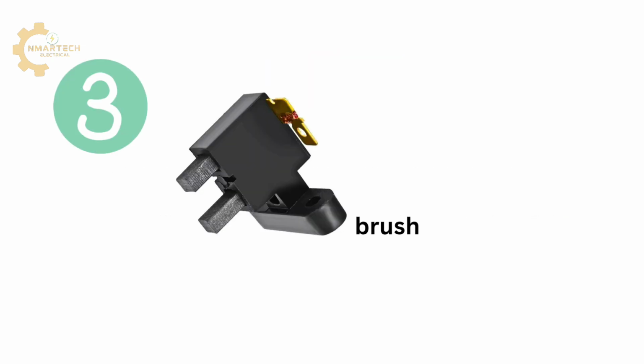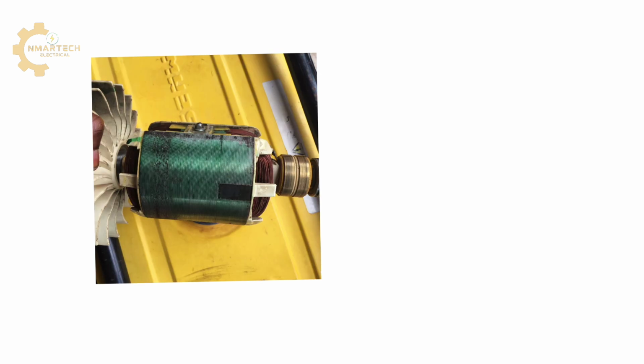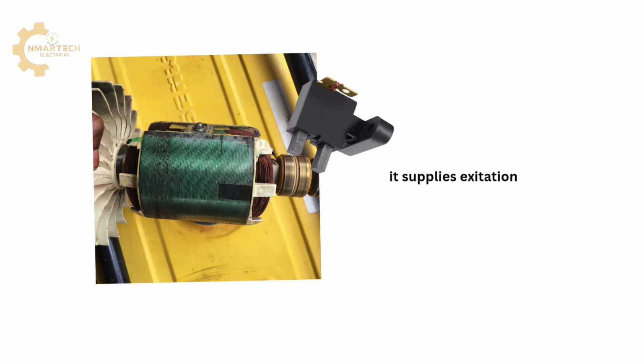Number 3 on the list is the brush. This very component supplies DC excitation voltage from the AVR to the armature. It is made of graphite and conducts from the slip rings to the coil of the armature.